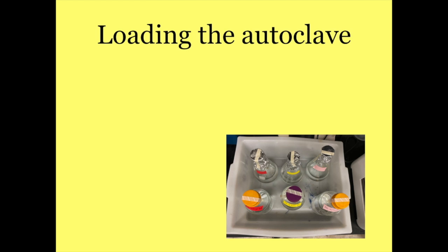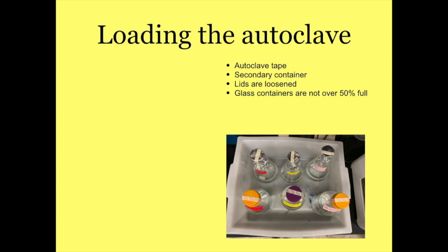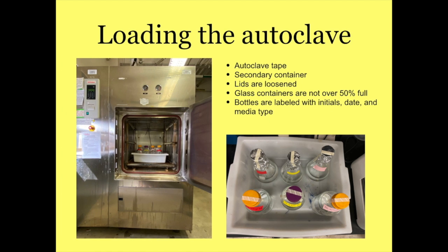In order to load the autoclave, we have to make sure that we have provided autoclave tape and a secondary container. We have made sure that all the lids are loosened, the glass containers are not over 50% full, and that our bottles are labeled with initials, the date, and the media type. Now we are ready to load our supplies into the autoclave.